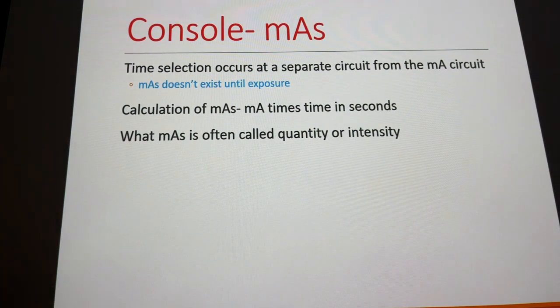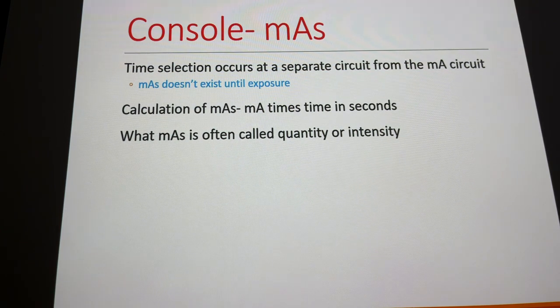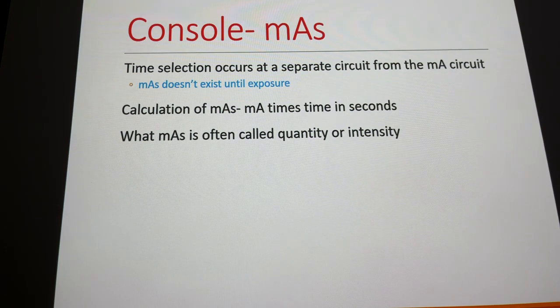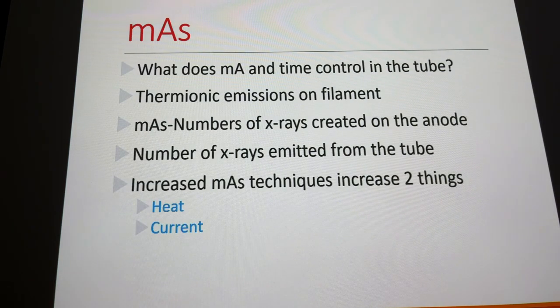As you increase MA, you're sending more electrons through the filament — you don't have tube current yet, just filament current. MA stands for milliamperage, and amperage is just a count of electrons. Increase your MA and you're increasing the count of electrons going through the filament, essentially making the filament hotter — like turning up the temperature on a toaster or oven.